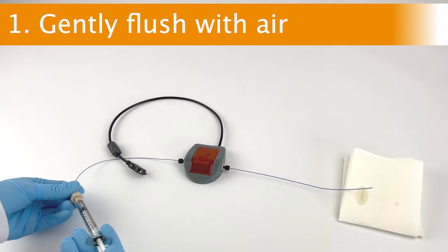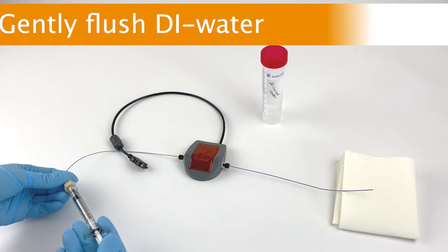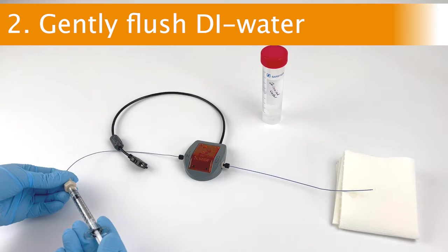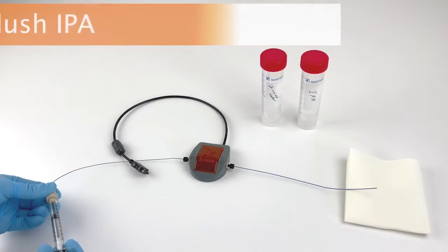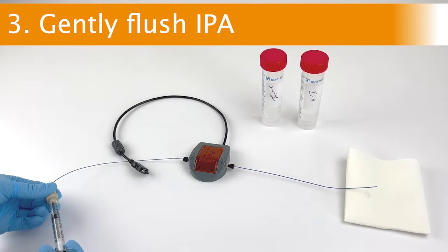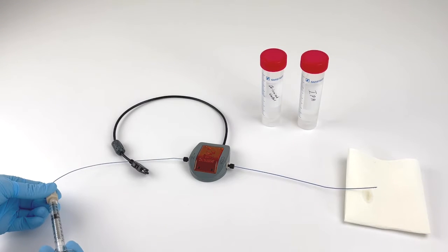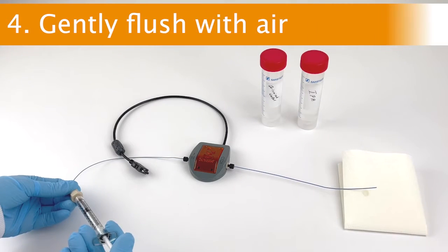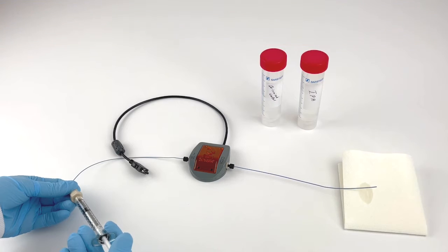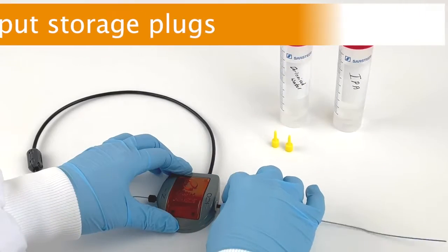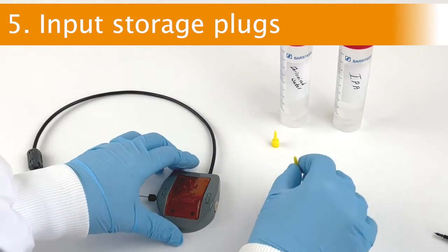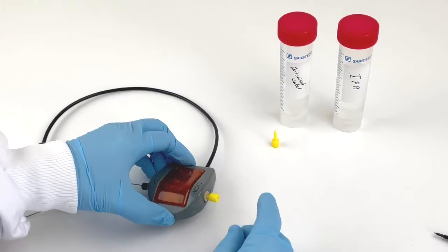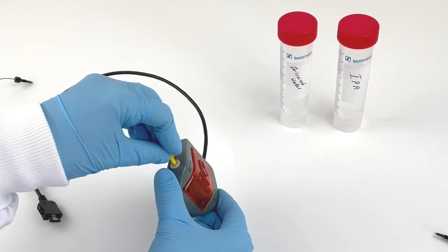1. Gently flush with air. 2. Gently flush with deionized water. 3. Gently flush with solvent such as IPA. 4. Gently flush with air again. 5. Close the input and output ports of the flow sensor with the plugs provided and store.